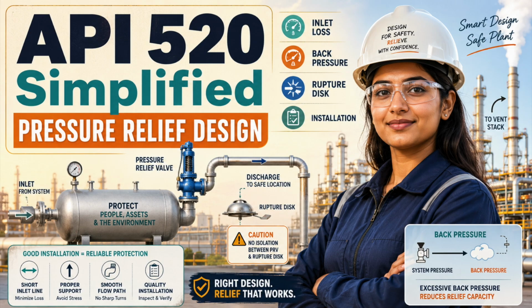When a rupture disc is installed upstream of a relief valve, the space between them must be managed. If the disc leaks and pressure builds in that interspace, the differential pressure available to burst the disc is reduced. The vessel may then have to reach a higher pressure before the disc opens. That hidden pressure can silently defeat the intended protection basis. The interspace needs suitable venting, indication, monitoring, or telltale detection. Never allow an unmonitored trapped pressure zone between a rupture disc and a relief valve.